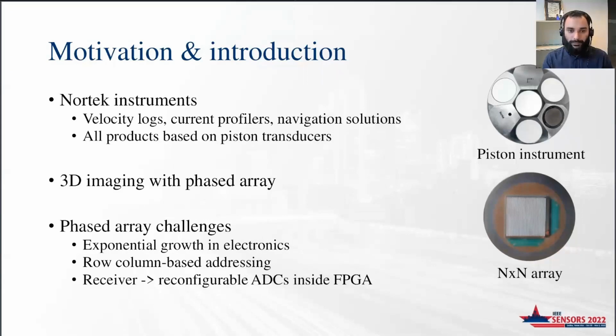When we talk about phased arrays, they give us the opportunity of 3D imaging, beam steering, beam focusing, and other exciting opportunities. However, these advantages which we get with phased arrays come at a cost of challenges, for example, exponential growth in electronics with the phased array. If we talk about a piston instrument, we have 3 to 5 transducers to process.